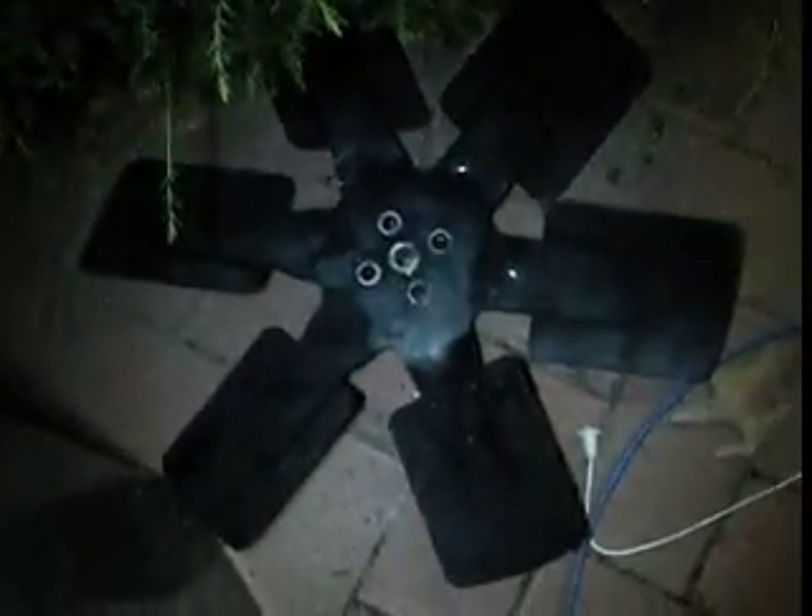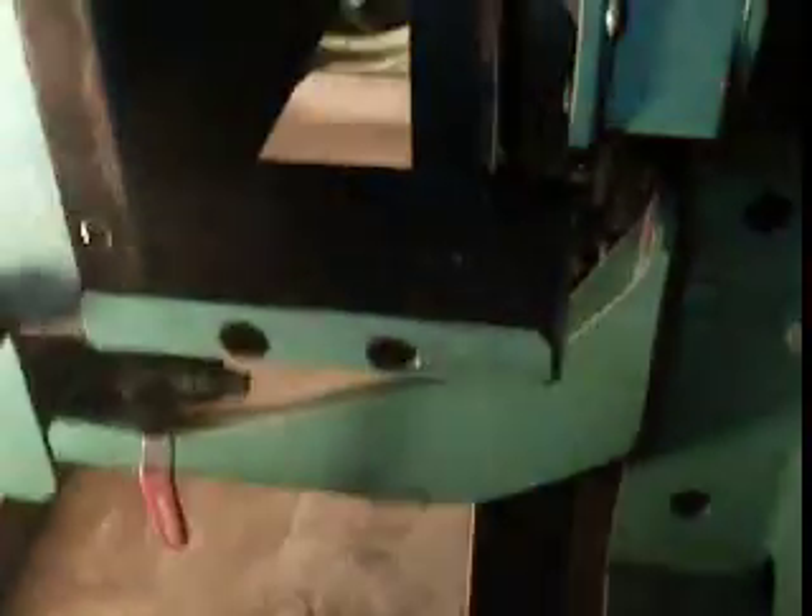Over here is the grill, and there's the fan, which should be green - but that ain't green. I've got a hose sticking outside here, and I've got an old air conditioning condensate tray that runs outside. So I'll wash it down. I'm going to replace the belt now that it's off. I've got to get a new one. It's getting a bit older and will definitely have oil on it.